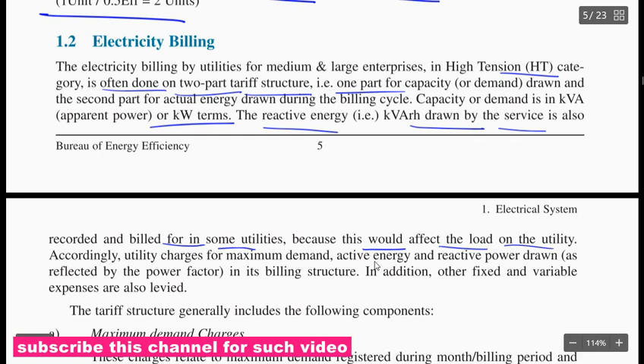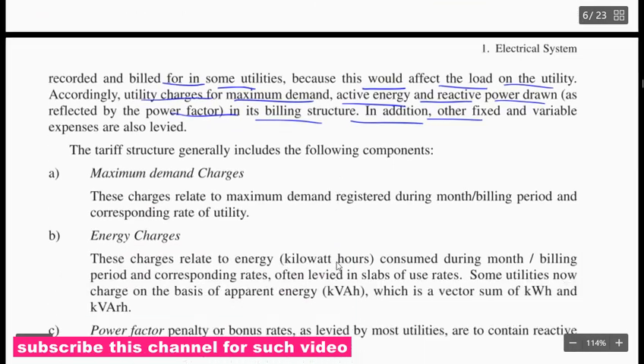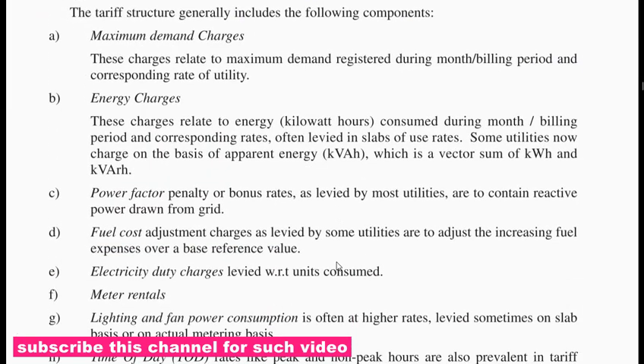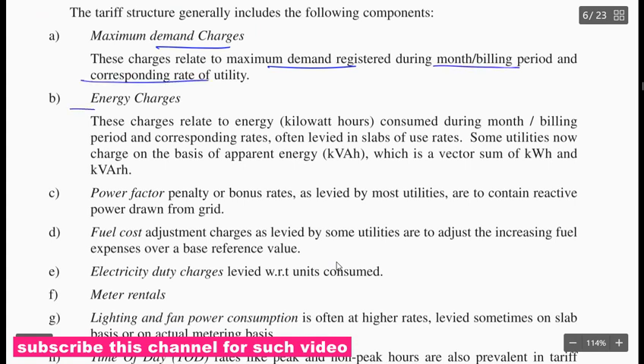affect the load on the utility. According to the utility, charges are levied for maximum demand. Active energy and reactive power drawn are reflected by the power factor in the billing structure. In addition, other fixed and variable expenses are levied, that is, maximum demand charge. These charges are based on the maximum demand registered during the month or billing period and the corresponding rate of the utility. Energy charge: these charges relate to energy in kilowatt hours consumed during the month or billing period, and the corresponding rates are often levied in slabs and as user rates.